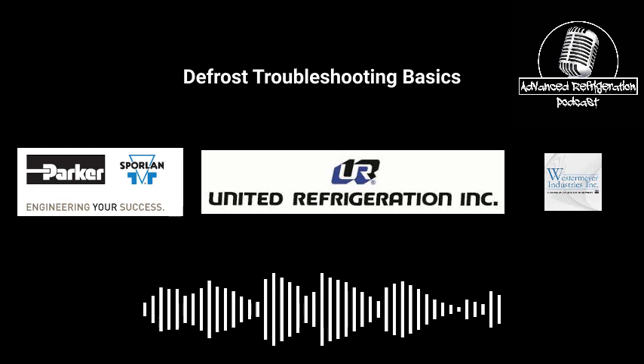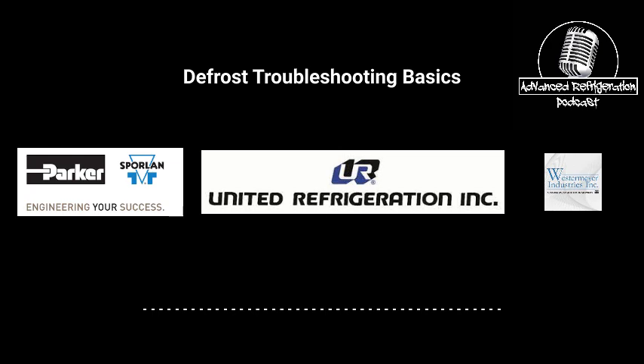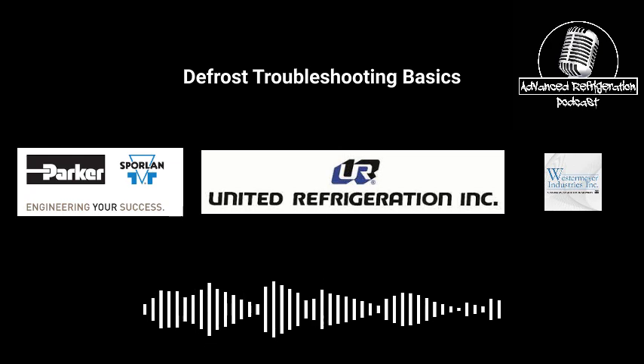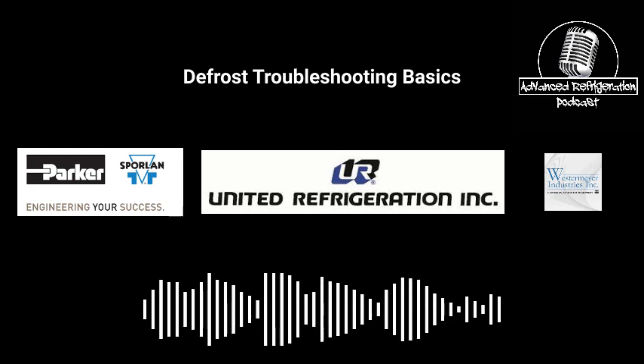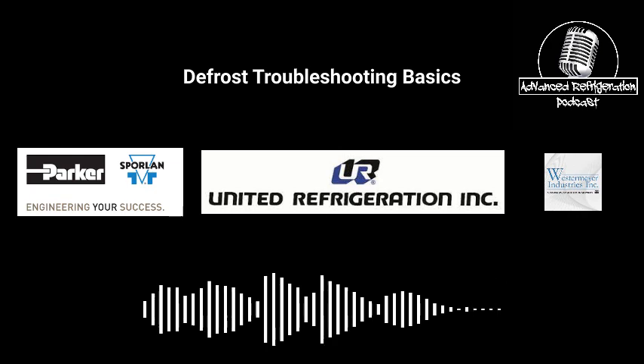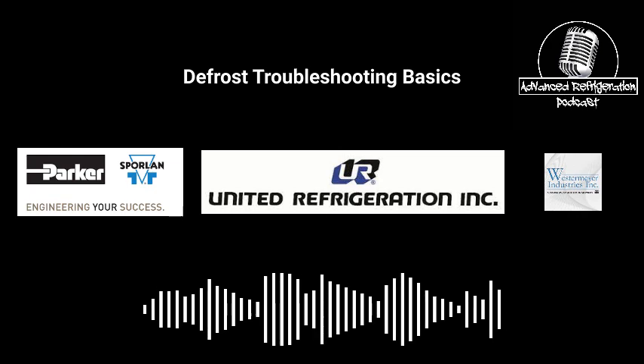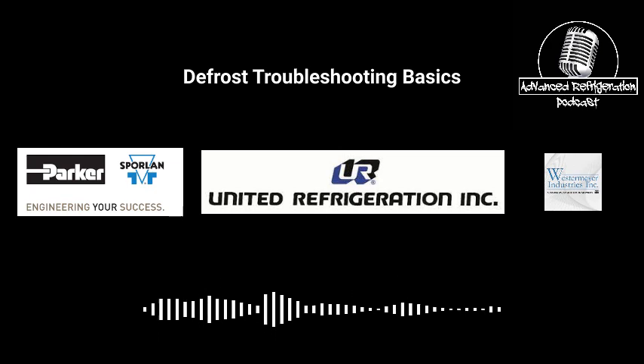Yeah, I flew out here to help start up another CO2 rack, because the manufacturer bailed on the startup and basically said they don't have anybody, so good luck. So I ended up having to cancel some plans and cancel a job and come out here to start this up, and then it slowly devolved into a mess like normal. A bunch of the coils that got installed were piped wrong from the manufacturer and had wrong valves in them.